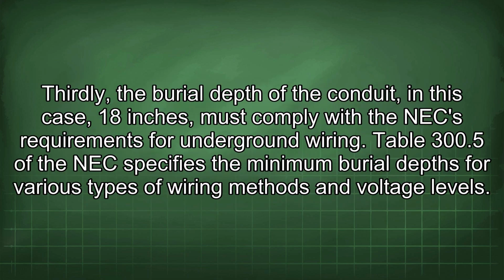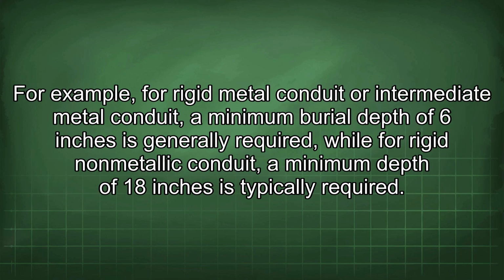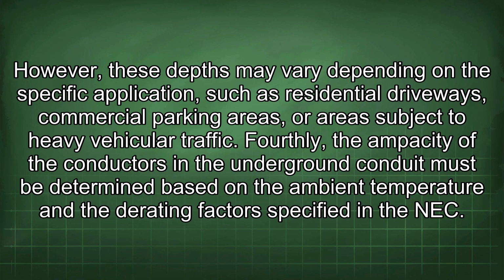Thirdly, the burial depth of the conduit, in this case 18 inches, must comply with the NEC requirements for underground wiring. Table 300.5 of the NEC specifies the minimum burial depths for various types of wiring methods and voltage levels. For example, for rigid metal conduit or intermediate metal conduit, a minimum burial depth of 6 inches is generally required, while for rigid non-metallic conduit, a minimum depth of 18 inches is typically required.